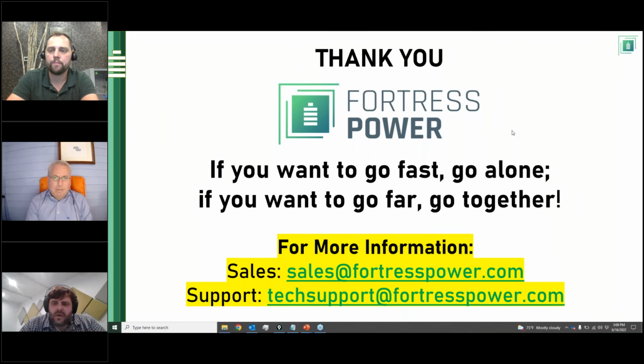I don't think code is driving batteries outside. When I talk about that, I'm referring to NFPA 855 dry wall requirements forcing batteries outside, and maybe in the future there will be minimum size room requirements for batteries too. But there are certainly jurisdictions that want the batteries in an outdoor setting regardless of the impact on the battery.